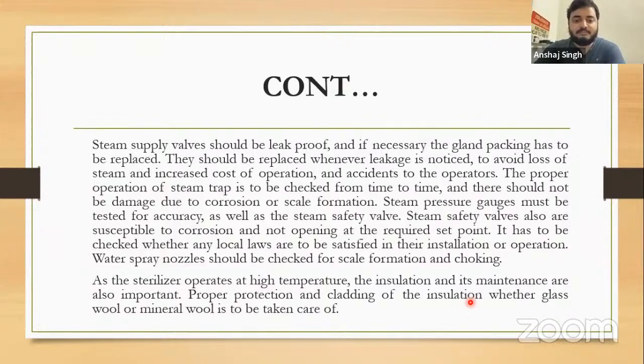The proper operation of steam trap is to be checked from time to time, and there should not be damage due to corrosion or scale formation. Steam pressure gauges must be tested for accuracy, as well as the steam safety valve. Steam safety valves are susceptible to corrosion and not opening at the required set point. It has to be checked whether any local laws are to be satisfied in the installation or operation. Water spray nozzles should be checked for scale formation and choking.